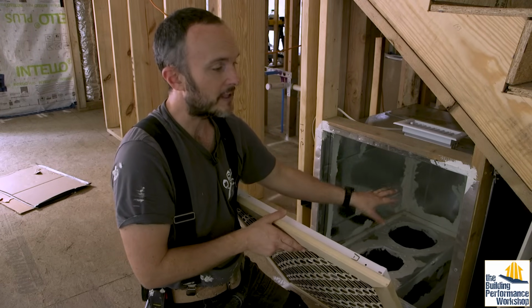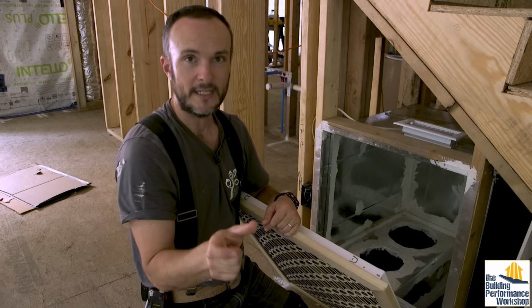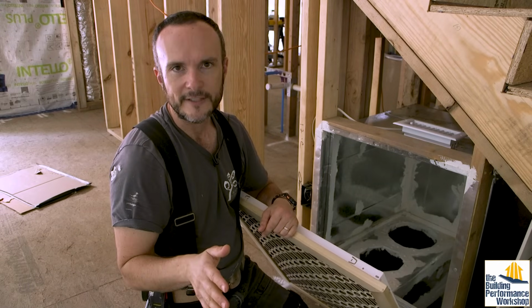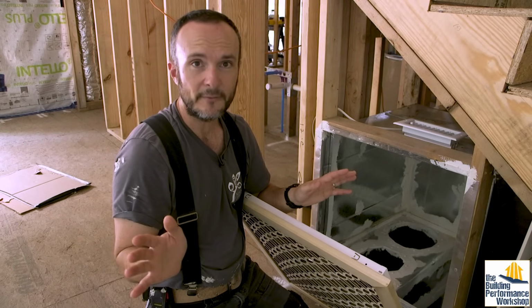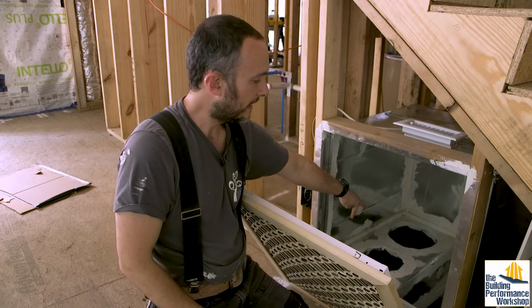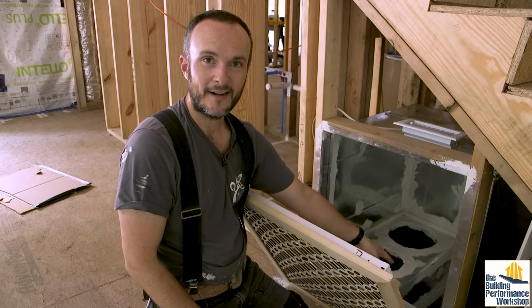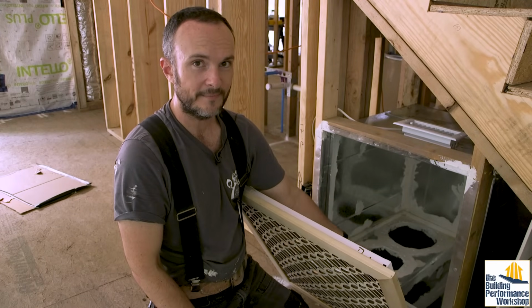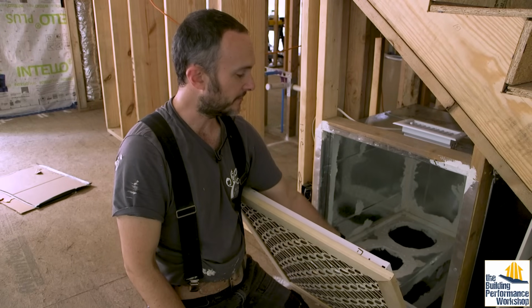The filter drop across the 2-inch MERV 13 filter is going to be something on the order of 0.2 inches of water column. That's a little high for a filter, but it's probably fine for me to deal with, because number one, both of these machines have their own built-in fan, and that machine right there, the Mitsubishi, can deal with up to 0.8 inches of water column for total external static pressure.